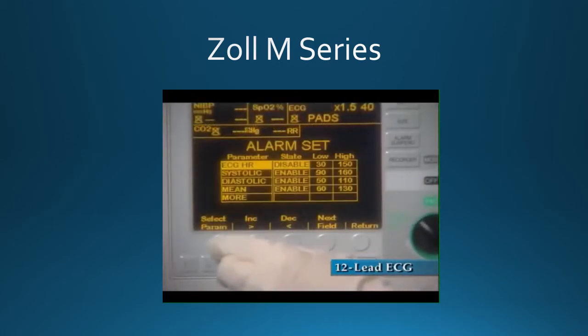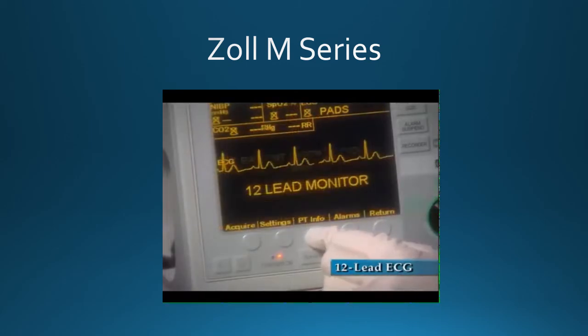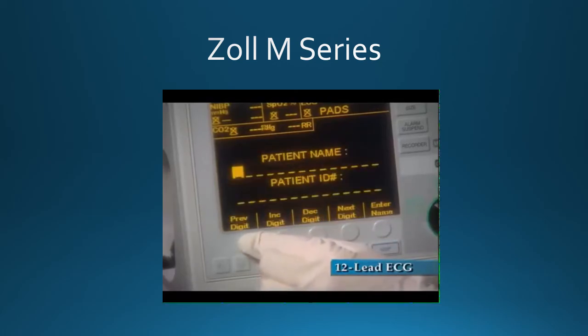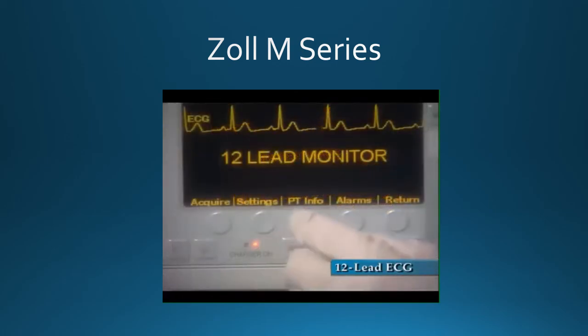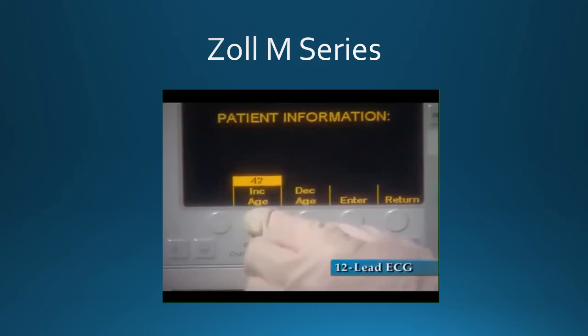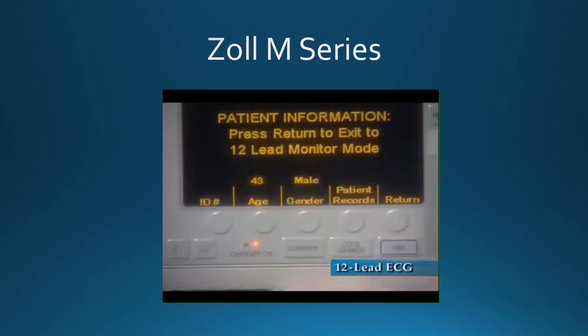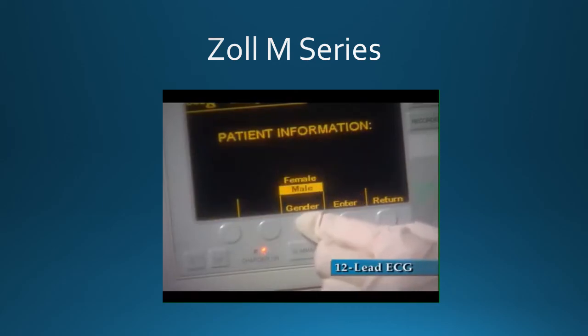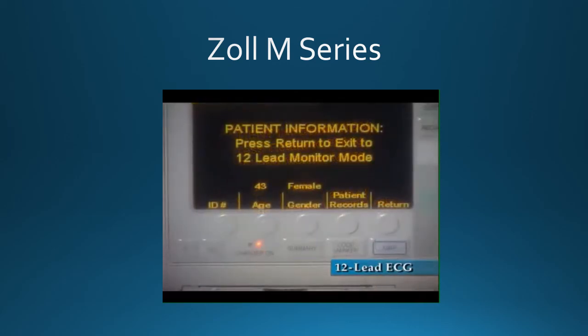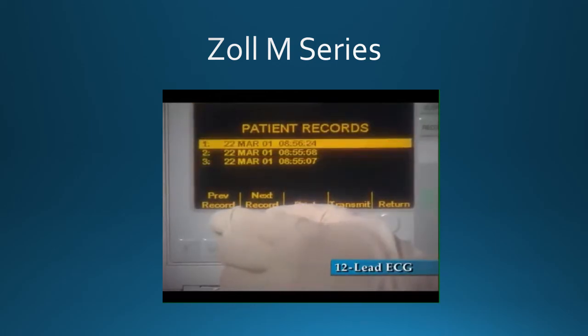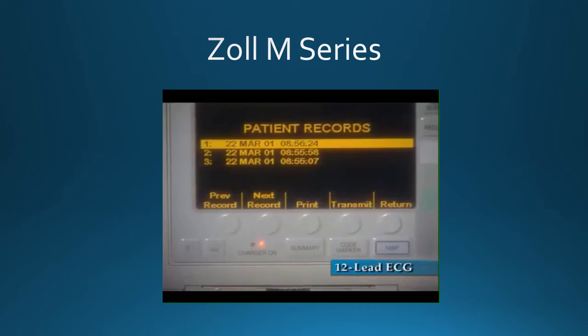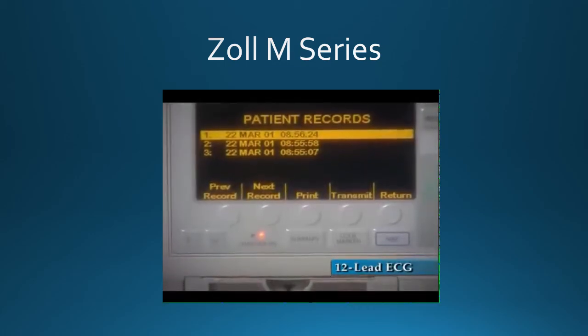Press the Alarms soft key to display the Set Alarm screen and corresponding soft keys. This screen allows users to enable or disable alarms. Pressing the Patient Information soft key allows the user to enter pertinent patient data, such as the patient's name and ID number. Pressing the Age soft key allows the user to enter the patient's age. The Gender soft key is used to identify the patient as male or female. The Patient Record soft key allows for reviewing, printing or transmission of a previously stored 12-lead recording. Pressing the Return soft key returns the operator to the previous screen.